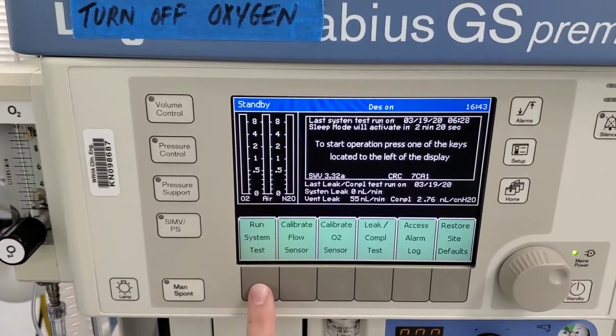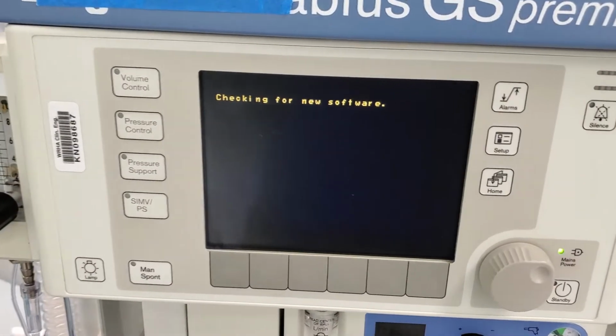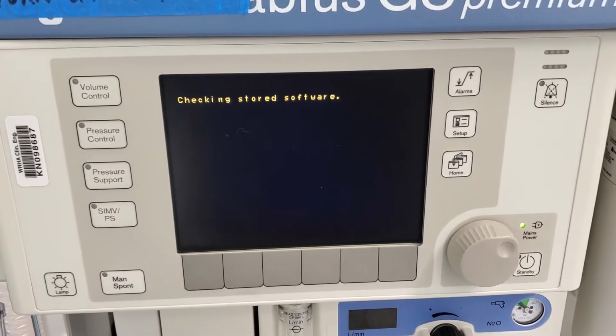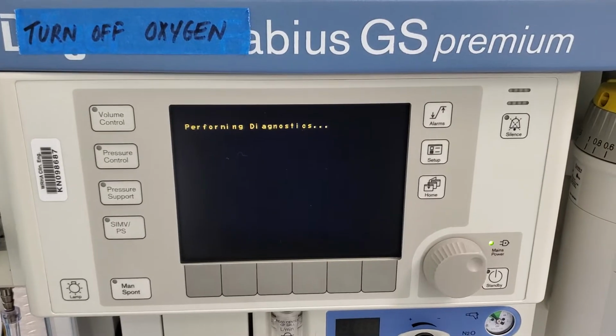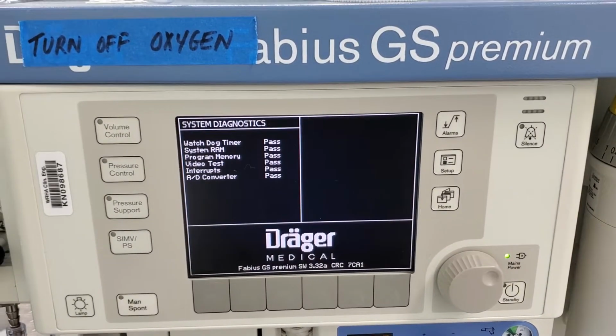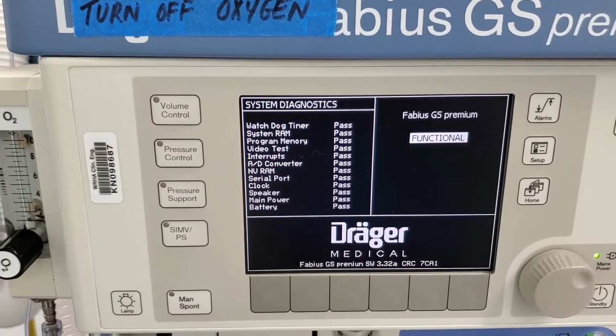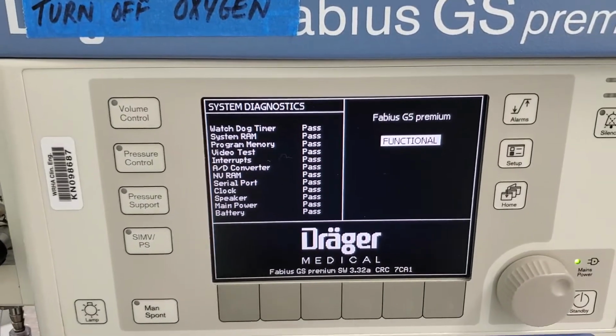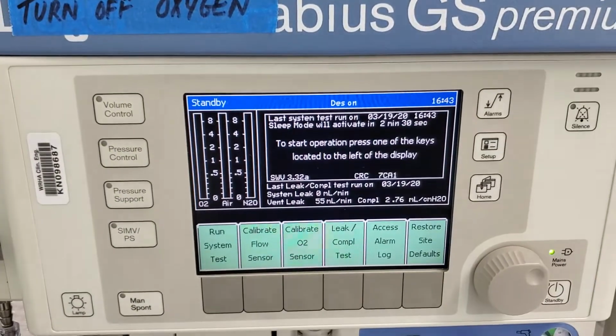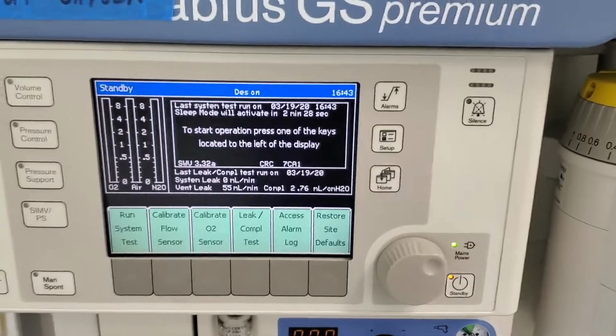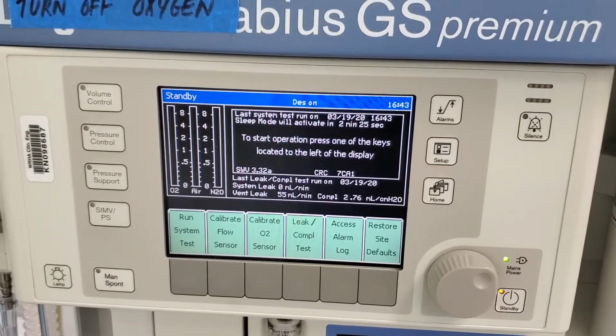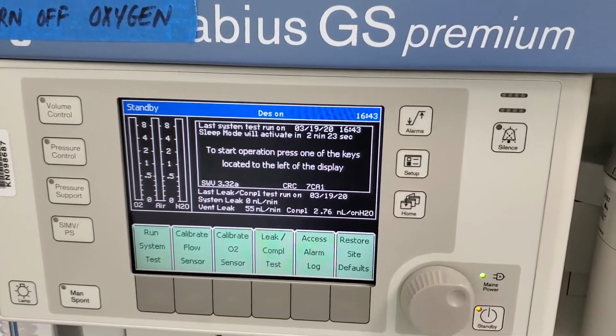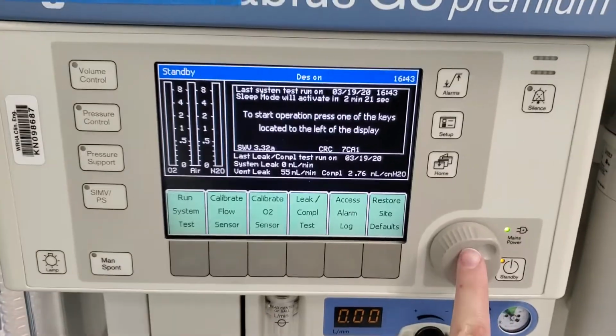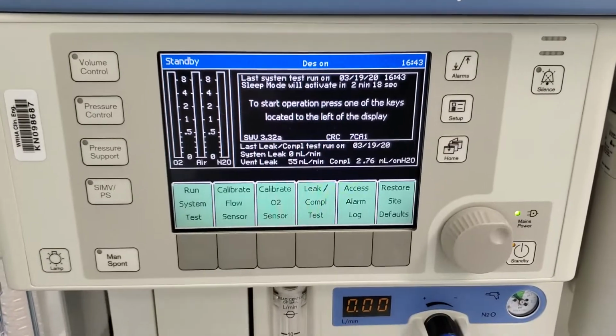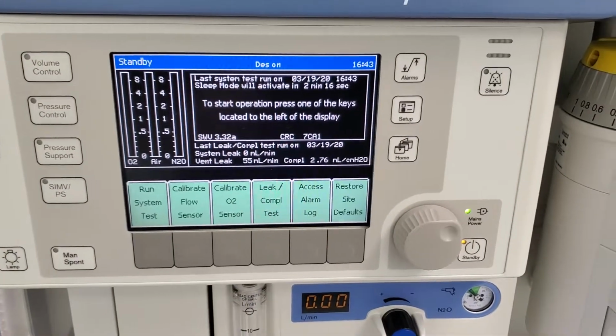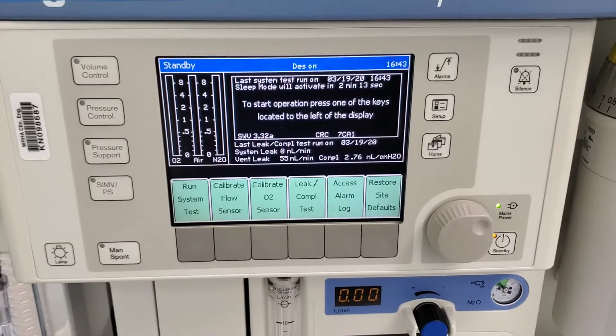The first test is the run system test, and this basically checks the electronic components and the software, making sure that the machine is deemed functional and safe for use. There's 10 different tests that it goes through. If everything passes, it'll say functional. If one does not pass, it'll categorize it into conditionally functional or non-functional. If it's conditionally functional, you have to acknowledge it by pushing the knob to get it into the home screen. If it is non-functional, then you cannot use the ventilatory modes on the ventilator.